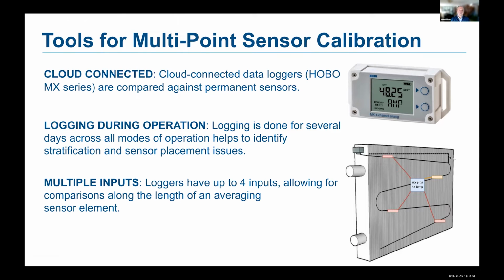You have a sensor installed in a piece of equipment. In general, we've been focusing on air handlers, and you want to compare that sensor to a known standard. And you think, well, okay, you compare it, and then if it's different, you put an offset on the sensor. But we often find that that isn't good enough in air handlers. And so we've been getting into multi-point sensor calibration, which I'll explain here. But these are the equipment that we're using to do that.